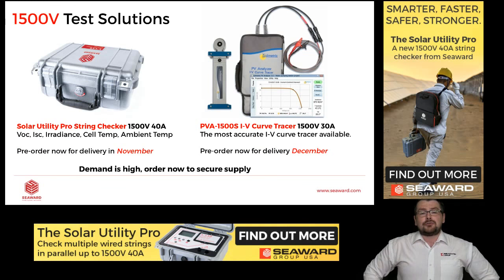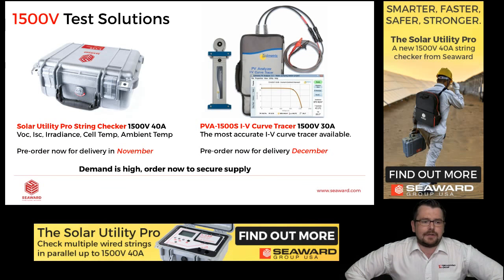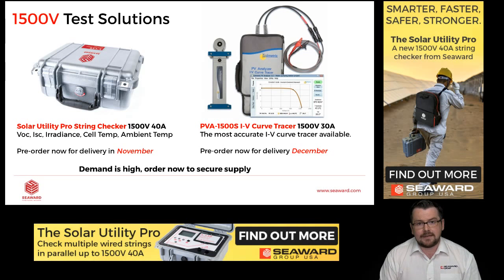There are also 1500 volt solutions available, and 1500 volts, which we will go into in the webinar, is becoming more and more prevalent in our industry. So we've created a solution of our own to help you very quickly and efficiently check the performance of these arrays. So the Seaward Solar Utility Pro String Checker is rated at 1500 volts, 40 amps. So it's incredibly useful for testing multiple strings in parallel, particularly when we have multiple strings going into a single fuse in the combiner box, which we're also going to cover in the presentation.